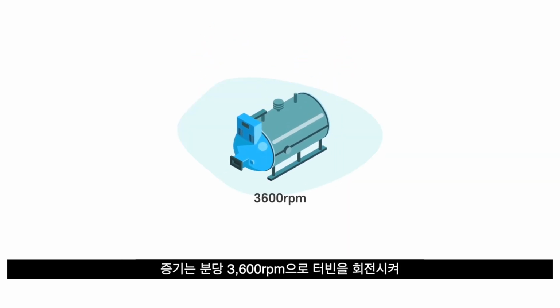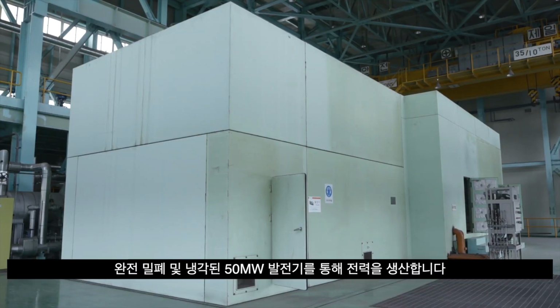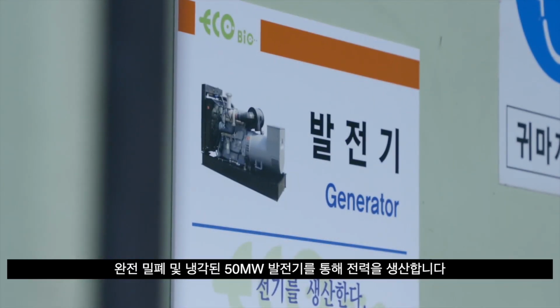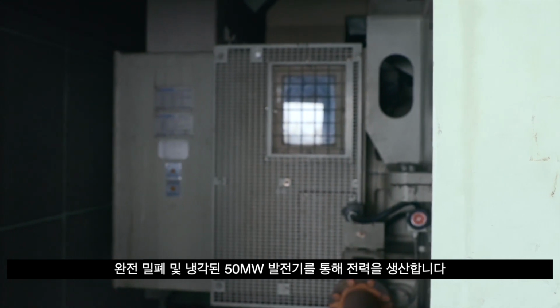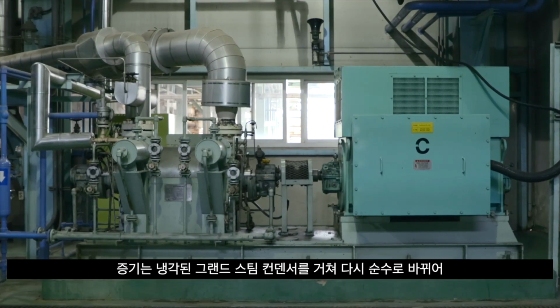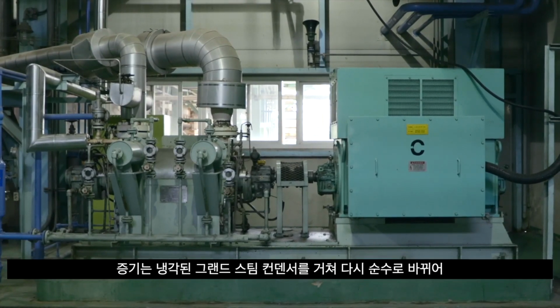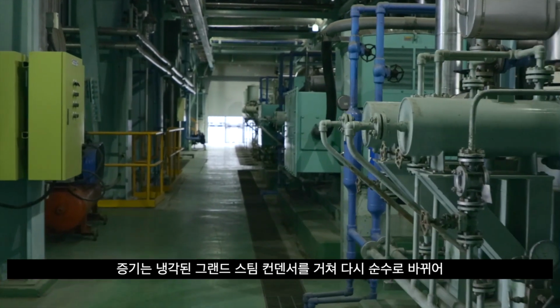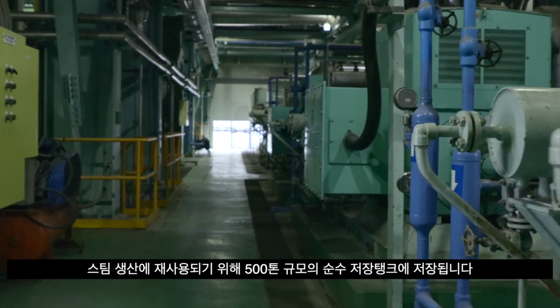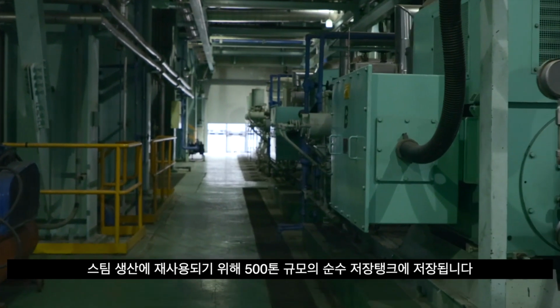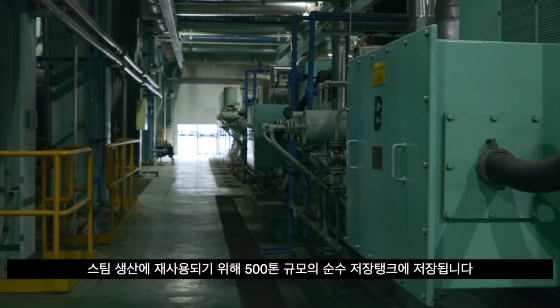The steam drives a turbine rotating at 3,600 RPM to generate electricity through a 50 megawatt generator, which is completely enclosed and air-cooled. Steam is routed to a gland steam condenser where it is cooled, transformed back to water, and stored in a 500-ton capacity pure water storage tank to be used again for generating steam.